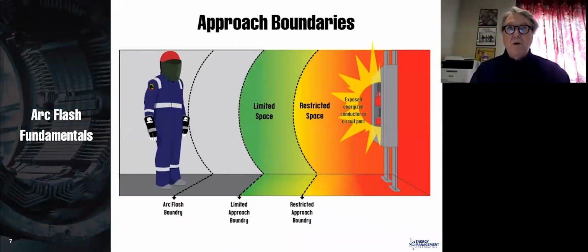These are the boundaries. You have one burn boundary and two shock boundaries. The burn boundary is determined by where you are at risk of a second-degree burn. That is 1.2 calories per square centimeter. So when you cross that arc flash boundary, if there were an arc flash, then you are at risk of second and or third-degree burns.